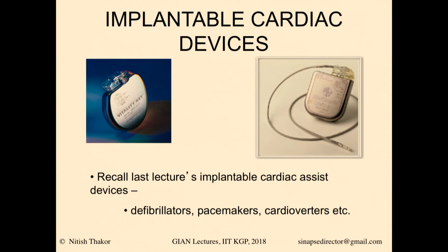So these kinds of O-ring connections are always the weak link. So this is a tremendous technology for making these kinds of feed-through connectors that are inert, and still, because you are inserting something into a titanium can, anything can leak through that, right? And so how do you keep it totally sealed and leak-free? It's very advanced materials technology. So there are, at least from outside, 2-3 parts like this long lead made of stainless steel or such, so it's compliant and flexible and still inert and can flap, because if the heart or brain moves, it's very compliant. And then this kind of plastic feed-through, and then the titanium can, and the feed-through has so many parts to it that it's hard to describe.